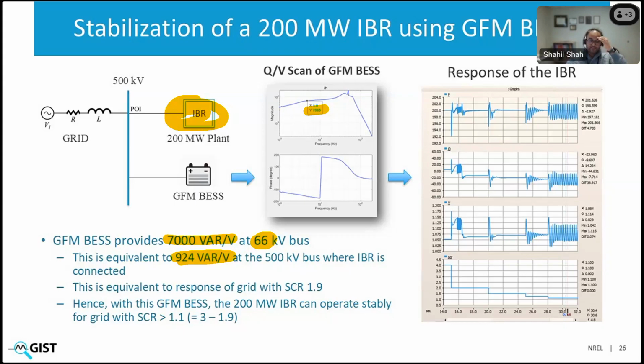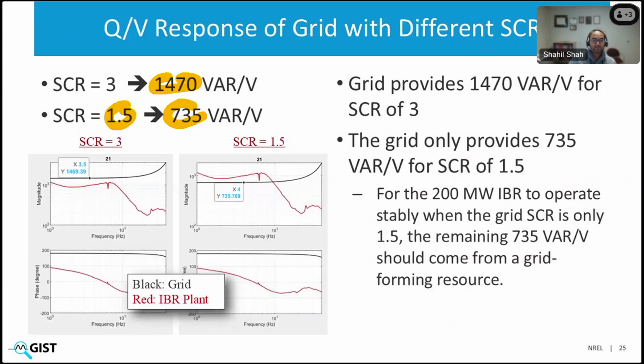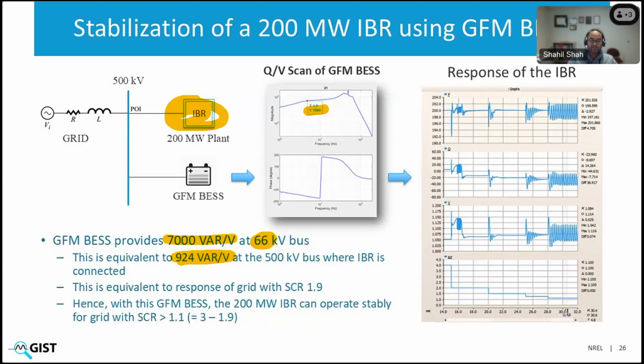So this is just a direct translation, of how much a 1 volt change in the 500 kV bus translates to change in voltage in the 66 kV bus. So 7,000 multiplied by 66 divided by 500 will give you this. And what it shows is that if I connect this grid forming BESS at the 500 kV POI bus, it will give me 924 var per volt of response. Now, from the previous slide, we found that there is a deficit of 735 var per volt of Q by V response to make the grid behave like it has a short circuit ratio of 3. So 924 is higher than 735. That means this grid forming BESS should be enough to meet our objective to stabilize this 200 megawatt IBR at SCR of 1.5.